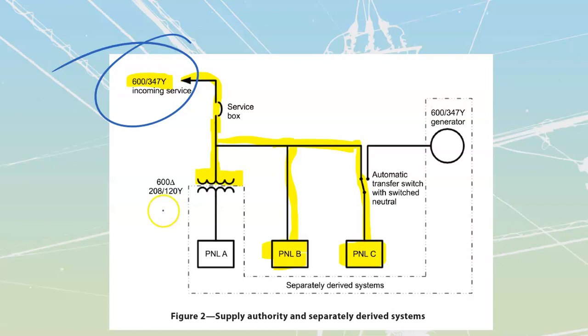It could be created through transformers, TX. It could be created through gensets. Over here, this genset is going to put out the same value of voltage, but we are creating it, so it's going to be a solidly grounded, separately derived system, or it could be through other things such as photovoltaics or inverters, wind power, run of the river, anything else that we create that is not coming in from our power authority. We see that all on this side over here, and that's going to be all of these.